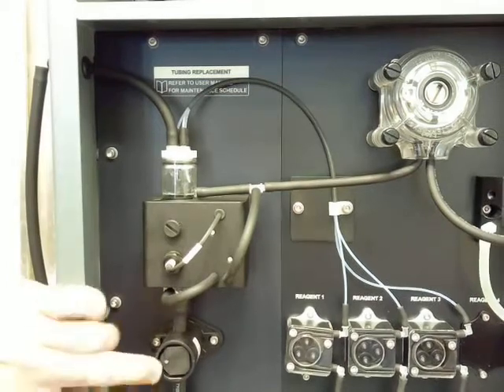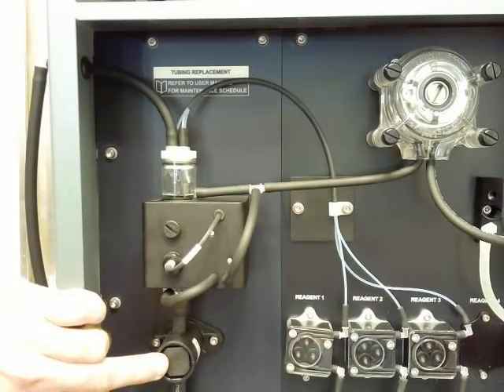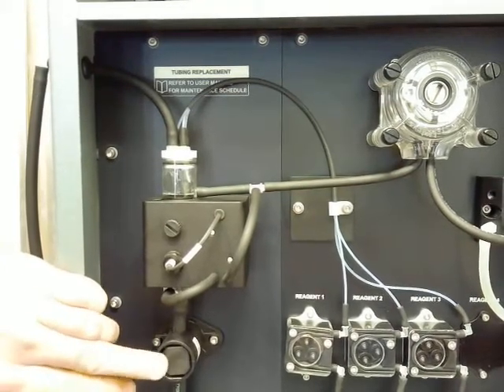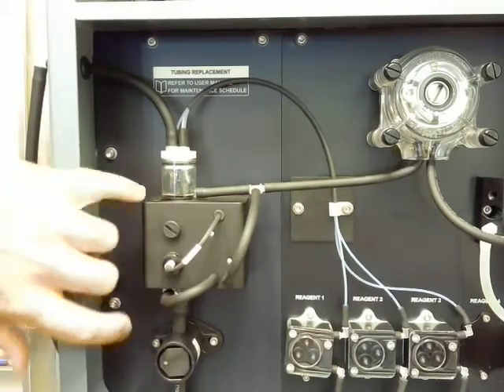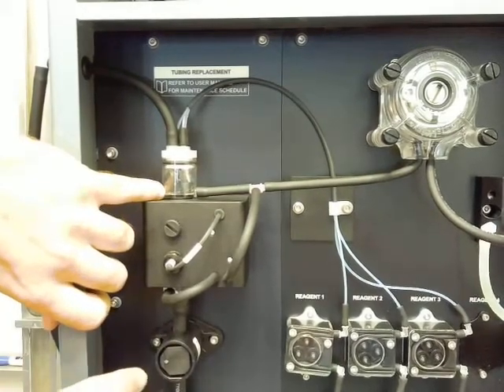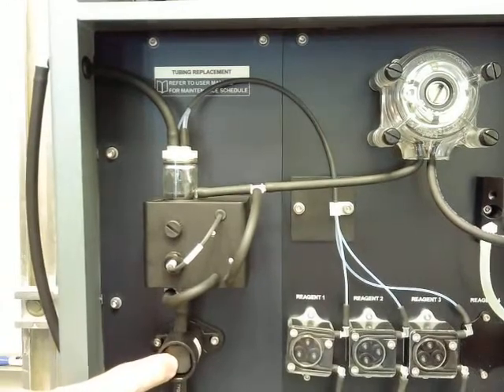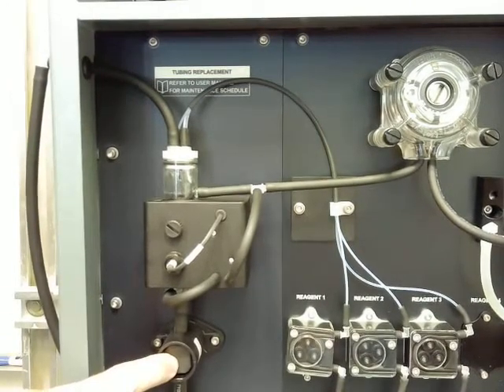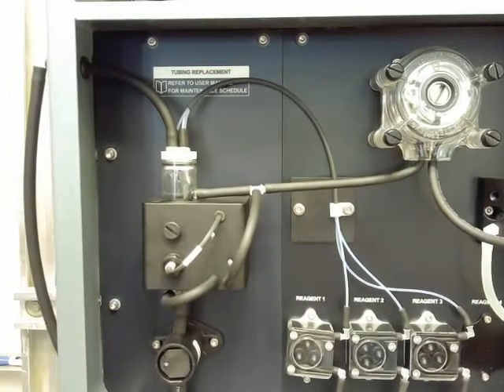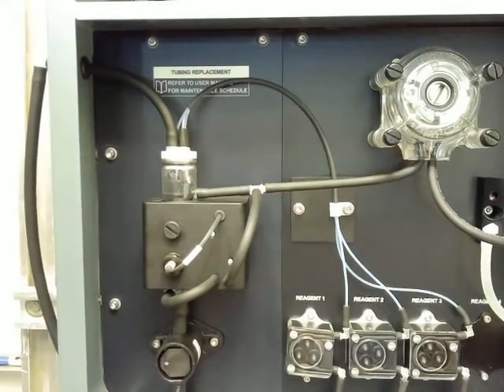Then on the bottom here, we have our drain pinch valve. You can manually activate this valve. If we watch our sample volume in our flow cell, if I just push this in, our sample is going to drain out the bottom of the flow cell. You can manually empty that cell should you have to for any reason. Just see how that process works.